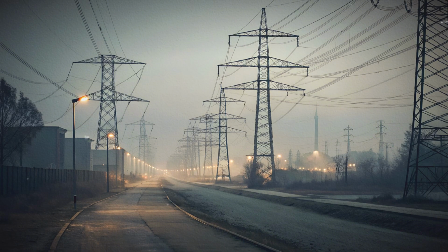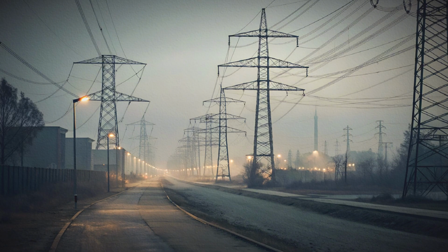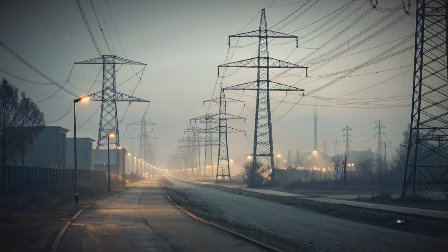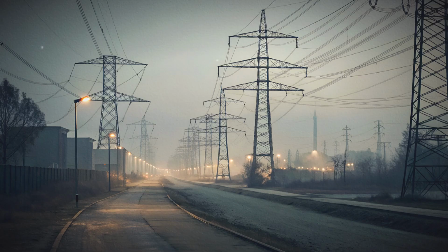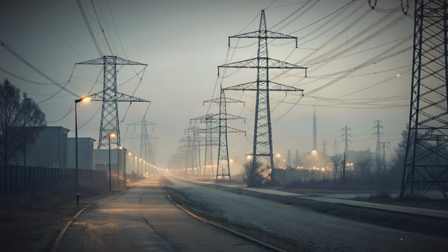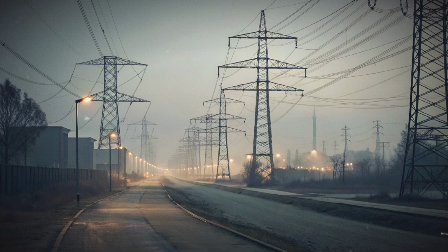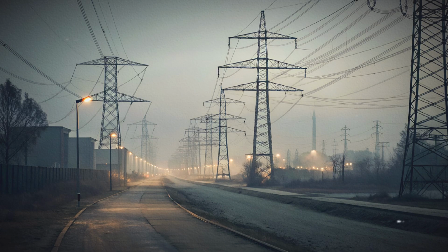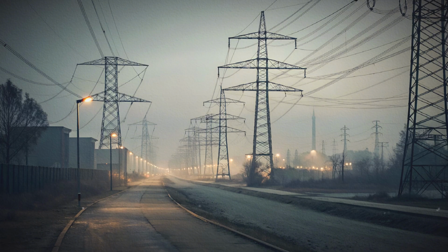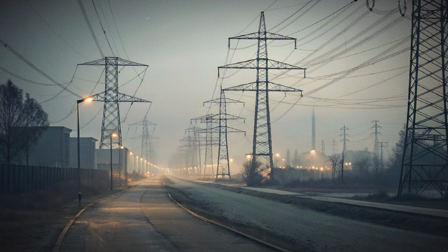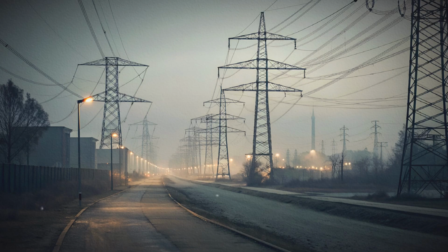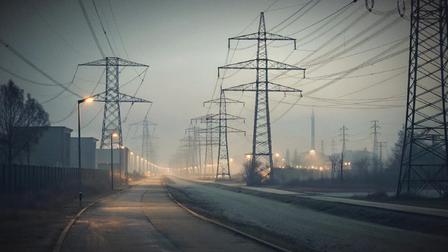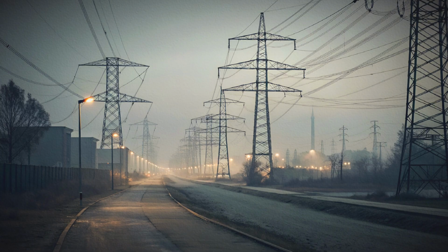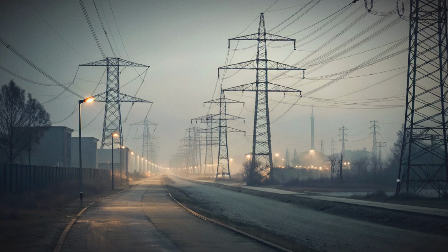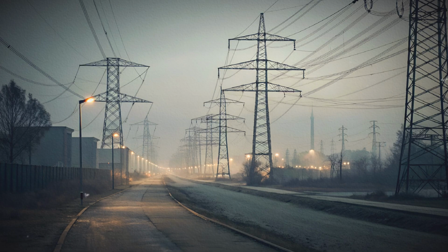Within a regional grid, control areas are established. Each control area is responsible for balancing generation and load inside its boundaries. Control areas are often called balancing authorities. They monitor generation, load, and the power exchanged with neighboring areas. The power exchanged occurs over tie lines. Tie lines are transmission lines that connect control areas. Operators set schedules for how much power will flow across these tie lines over defined periods. These schedules reflect planned exchanges for energy, seasonal needs, or market transactions. Maintaining flow close to the scheduled amount is part of normal operations.